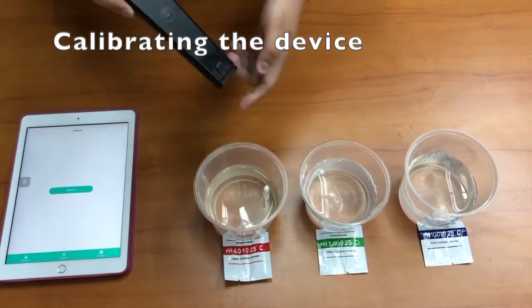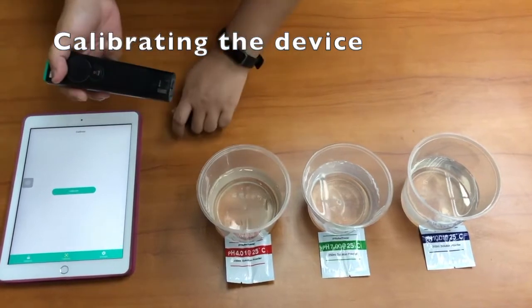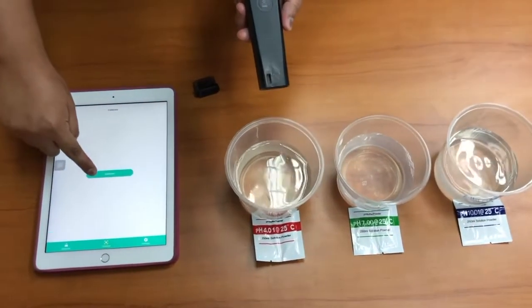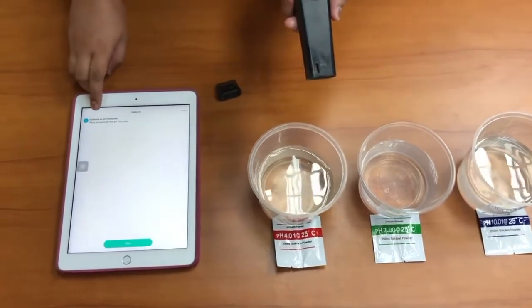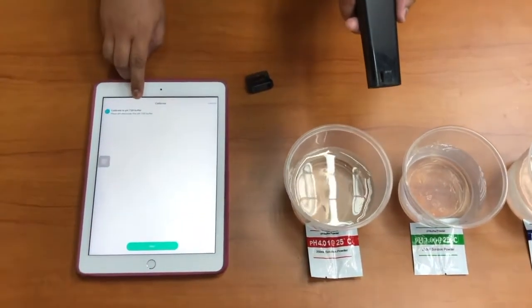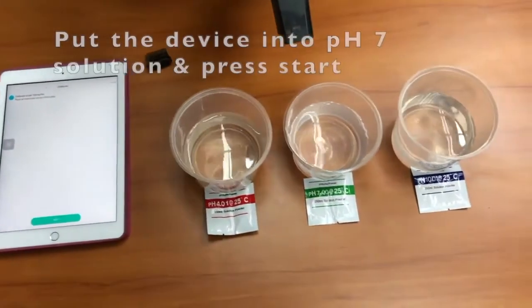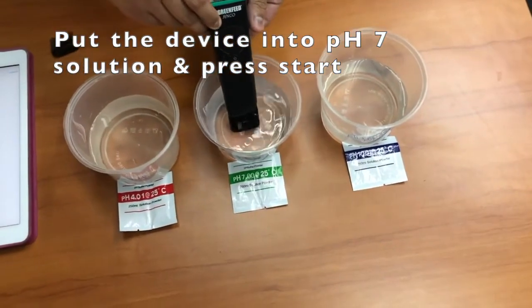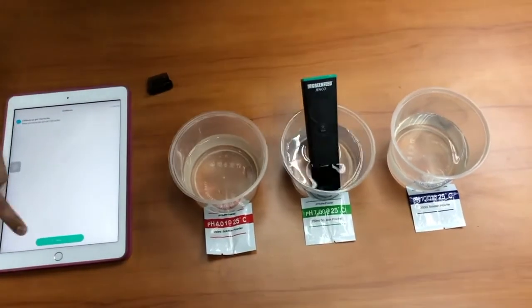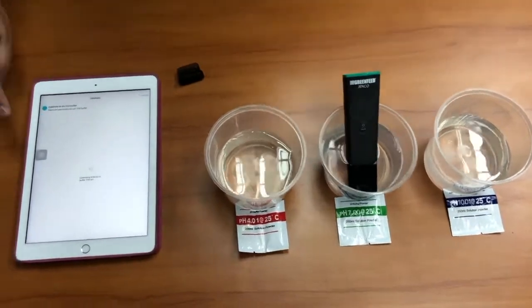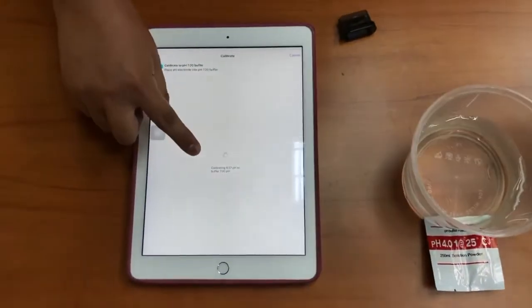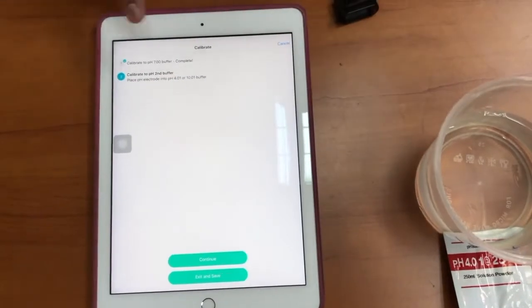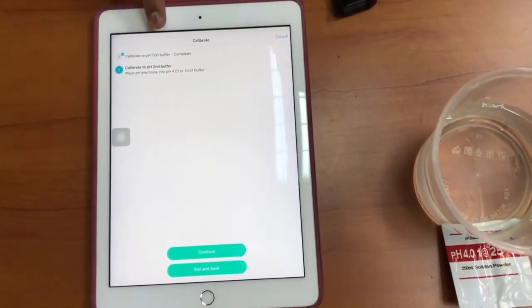We open it and from the app you click calibrate first. The first step is to calibrate to pH7 buffer. Now we put our pH meter into the pH7 buffer and start. The app is calibrating—you can see from here. After calibration is complete on pH7...